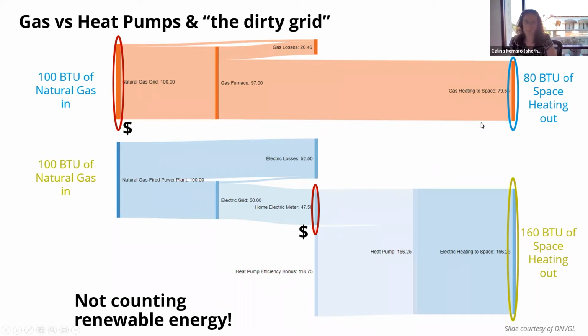So it's essentially like having an efficiency of 300 or 350 or 400% on that piece of equipment, instead of having this 80% efficiency from a boiler, which means that for this same amount of gas input at the power plant, once we get to site and we're able to pull that heat out of the air, the actual heat that goes into our space is more than the amount of gas we had to put in. And this is not accounting for any renewable energy at all. This was if the grid was entirely dirty. So this is why, as we're talking about decarbonization and responding to climate change, the push to move our mechanical and plumbing systems away from gas onto electricity, regardless of how fast it takes the grid to become more renewable.